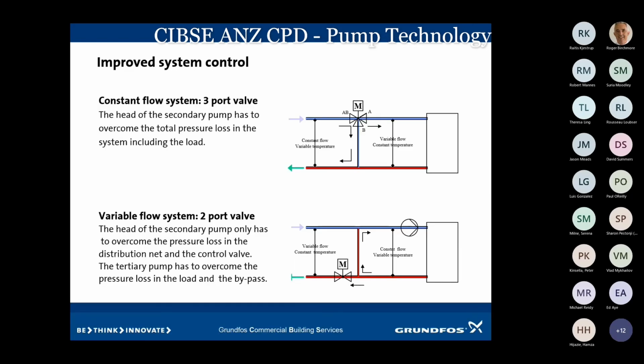Improved system control, and we've all seen it over the years. We used to have, and we still use, 3-port valves in certain applications because we need them, but as time's gone on, we've moved to 2-port control, and in 2-port control we now vary the speed of the pump to match the system, whereas when we use a 3-port valve on the top there, the pump doesn't know any difference. It's designed to push the water through the 3-port valve into the unit that it's supplying, or if the valve moves, it'll actually just send it back to where it came from. So the pump just carries on, not knowing any different.